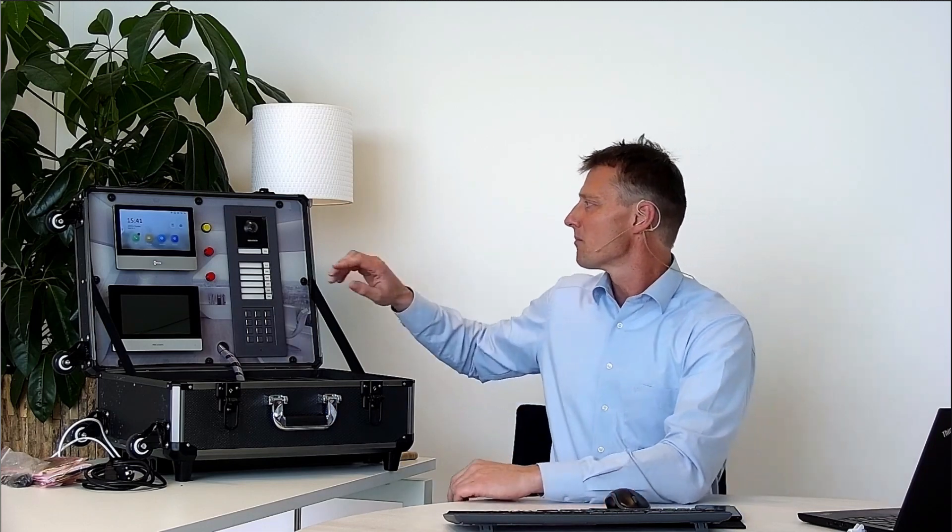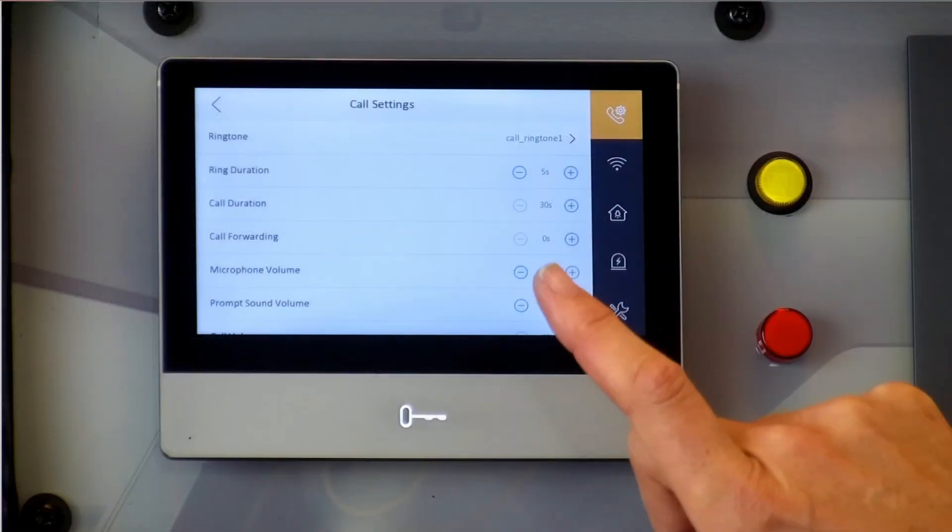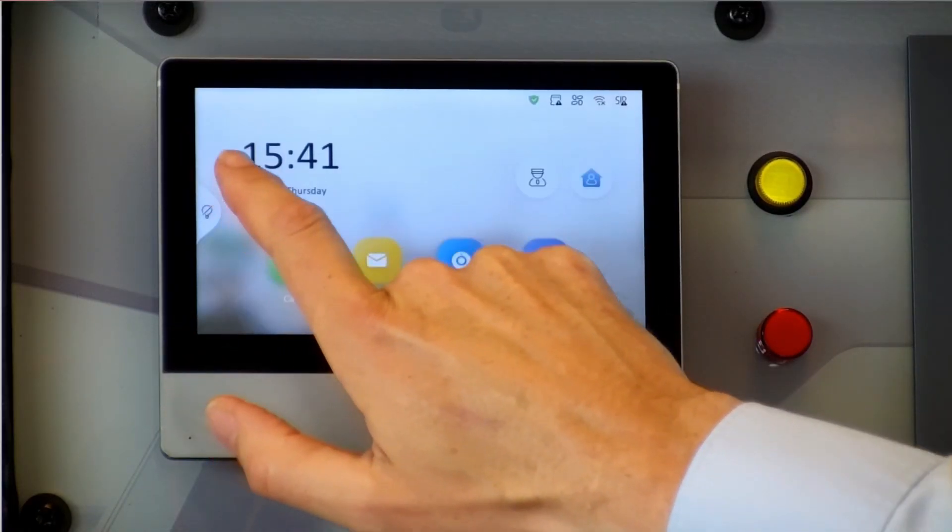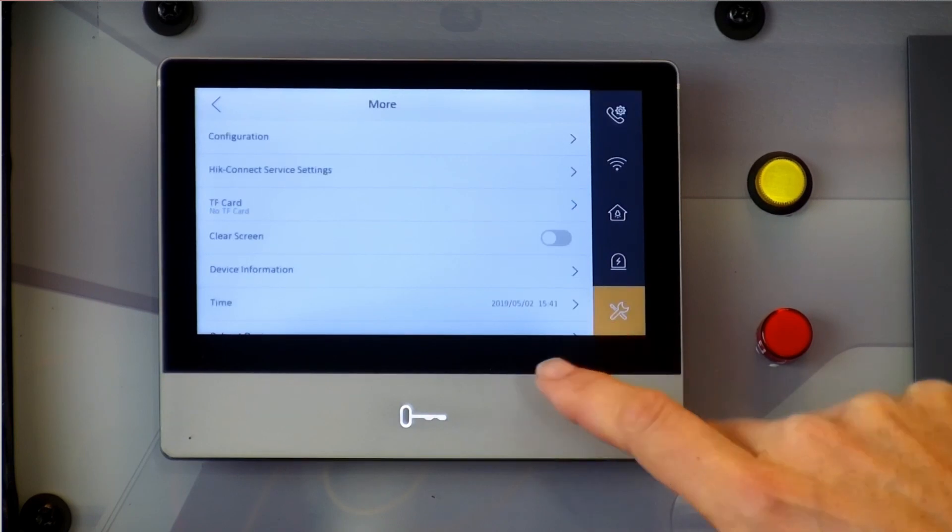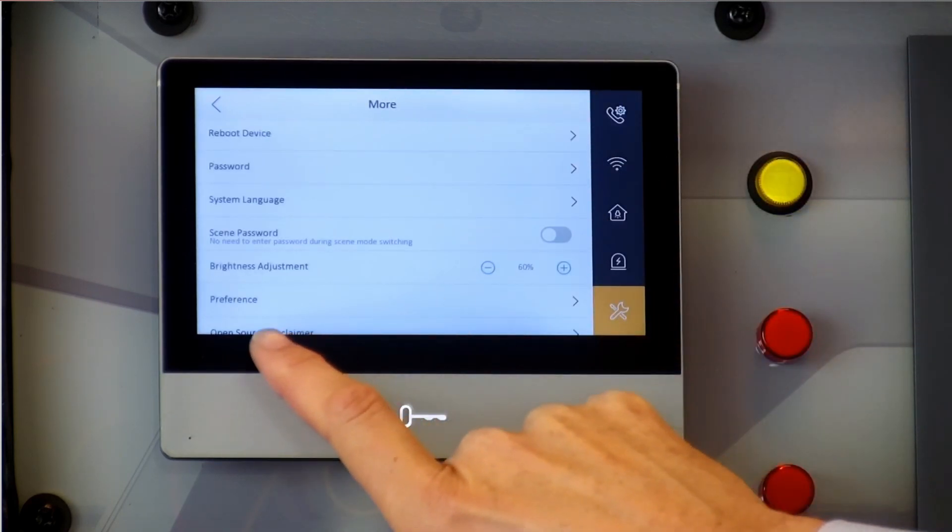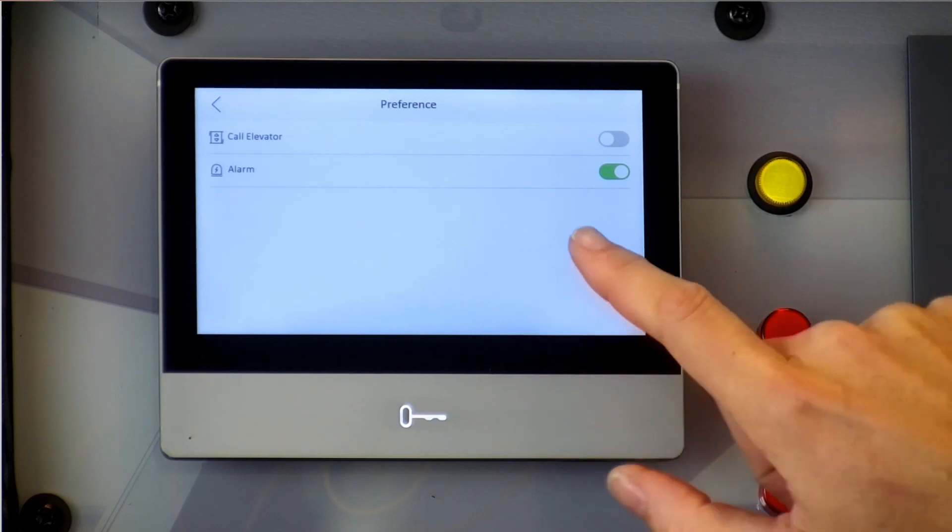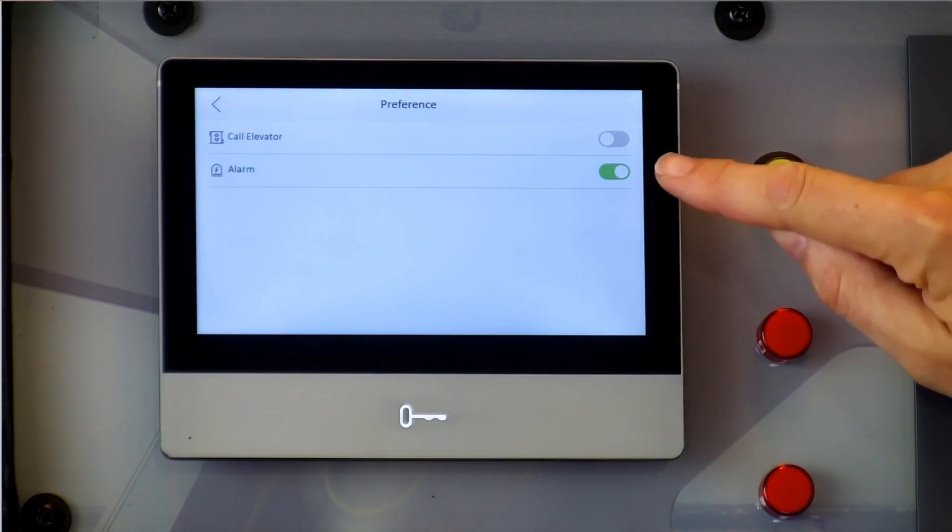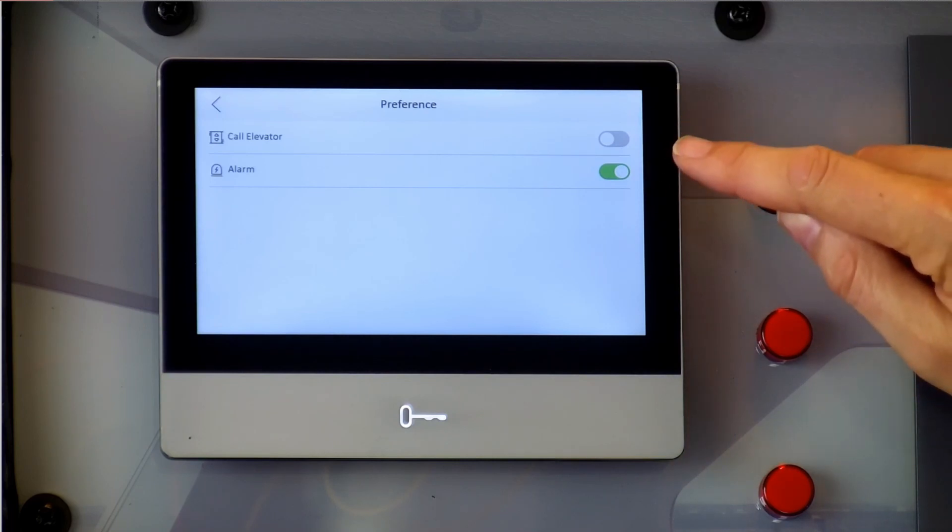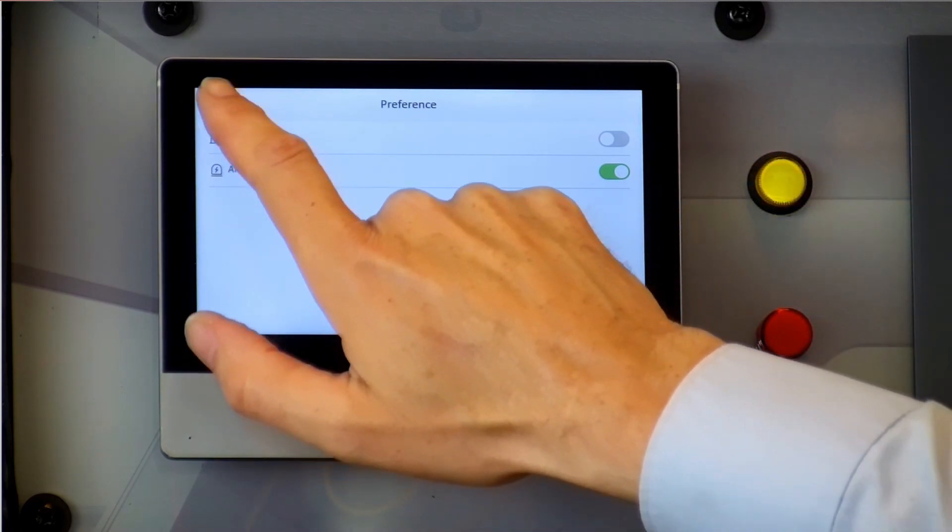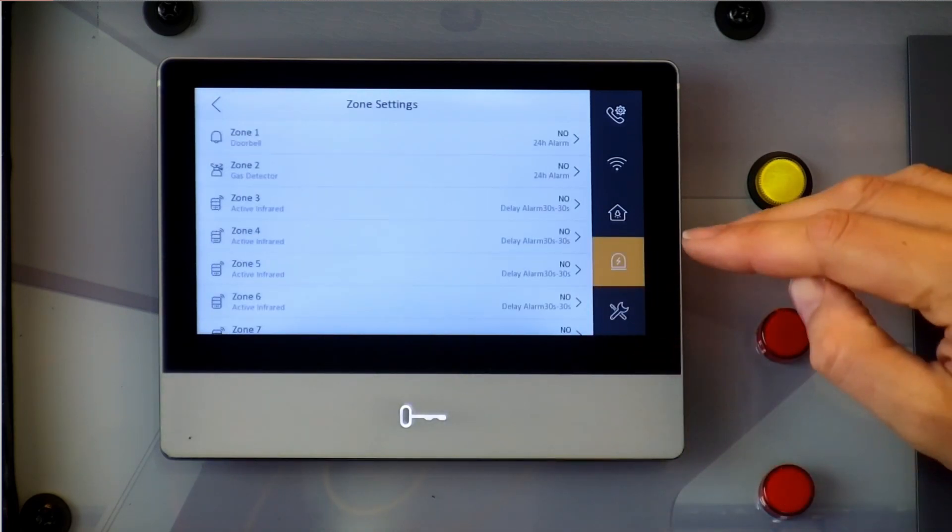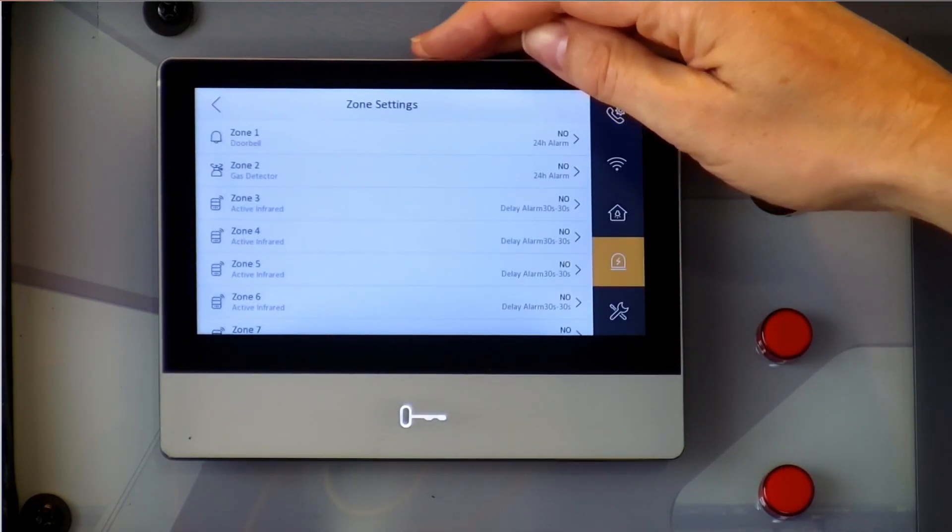Another thing I would like to explain is the alarm inputs. The door phone accepts eight alarm inputs and we can address them to any of those that we like. Before we can use the alarm inputs, please check in the control system if it's enabled. So we go to preferences and inside of preferences you can check mark the alarm. This means it will be visible and we can adjust it in the main screen.